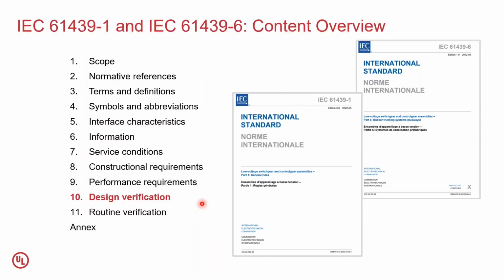And then you have the routine verification. You might ask where this routine verification is used. It is used by the manufacturers themselves. For example, for every busway that is shipped out, you might conduct an insulation resistance test, a very short duration dielectric test, or some physical checks. It is also used by third-party labs when they give a third-party certification mark. They may want to do certain routine verification before the products are shipped out. It may also be used by regulators to ensure that every product that gets manufactured, before it is shipped, undergoes some sort of pre-qualification non-destructive test.